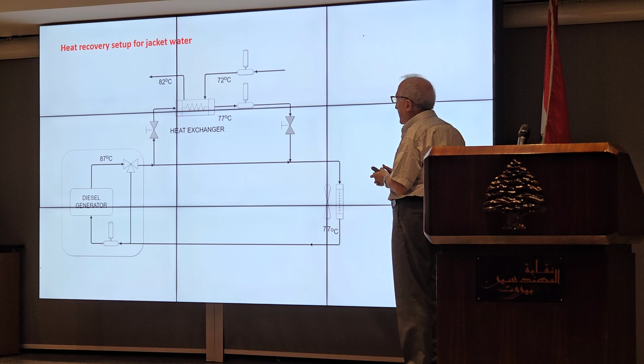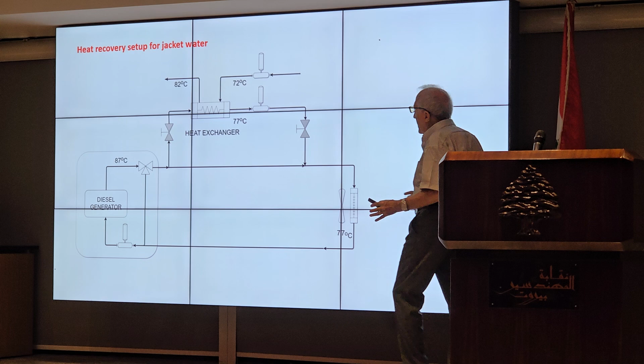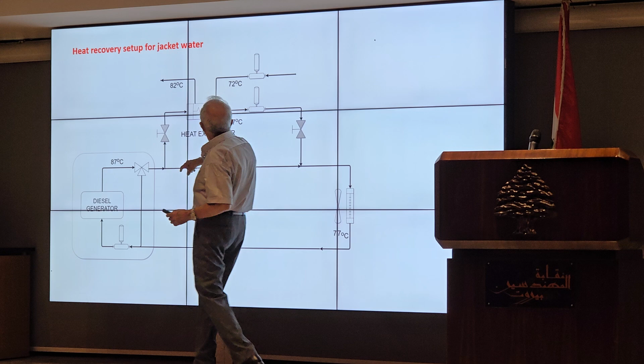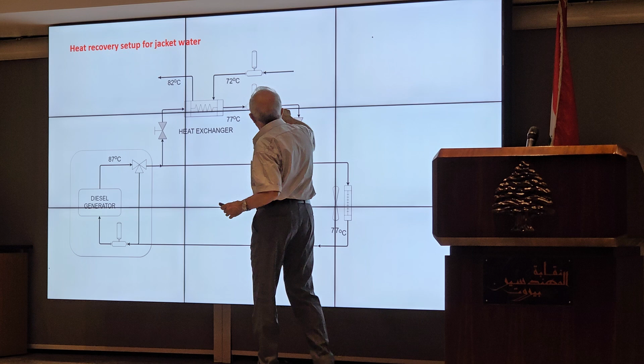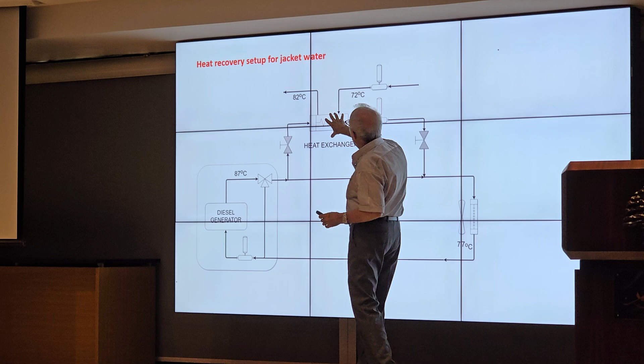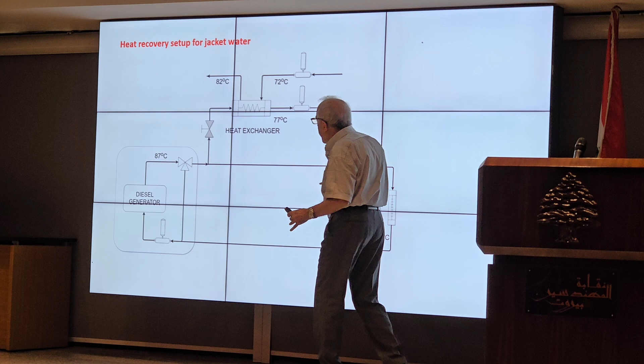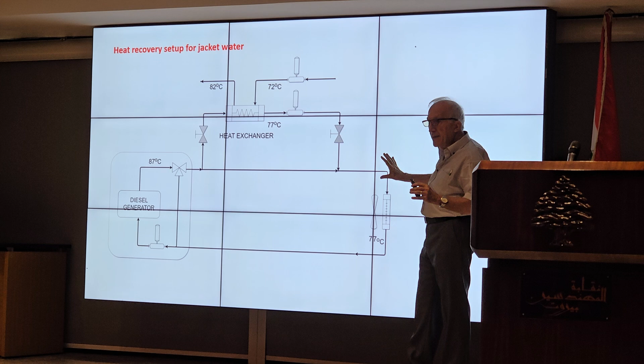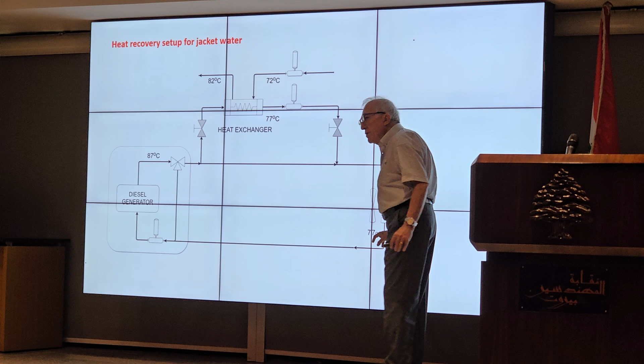This is the setup that we do for jacket water. Also here, we have installed these on brand new generators under guarantee, in some projects, and the easiest way to not interfere in the setup of the generator is this: the water coming out to the radiator, we pick it out and we re-inject it with this pump. So we take the heat, and if we are not cooling enough, this water goes back to the radiator of the generator. So nobody can argue that at one time we didn't cool the radiator sufficiently, because even if it passes by this, it will go to the generator.